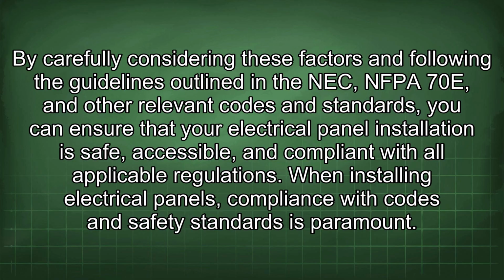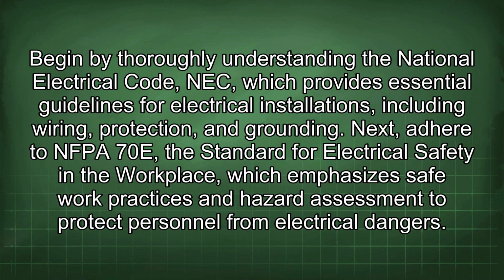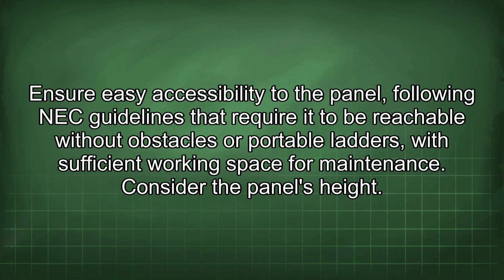When installing electrical panels, compliance with codes and safety standards is paramount. Begin by thoroughly understanding the National Electrical Code, NEC, which provides essential guidelines for electrical installations, including wiring, protection, and grounding. Next, adhere to NFPA 70E, the standard for electrical safety in the workplace, which emphasizes safe work practices and hazard assessment to protect personnel from electrical dangers. Ensure easy accessibility to the panel, following NEC guidelines that require it to be reachable without obstacles or portable ladders, with sufficient working space for maintenance. Consider the panel's height.